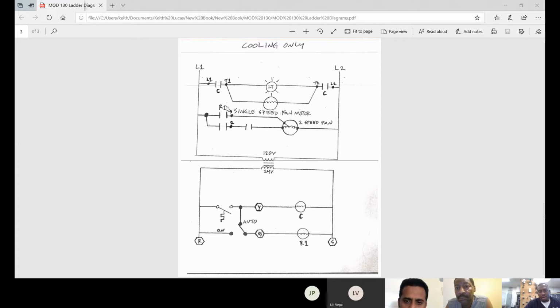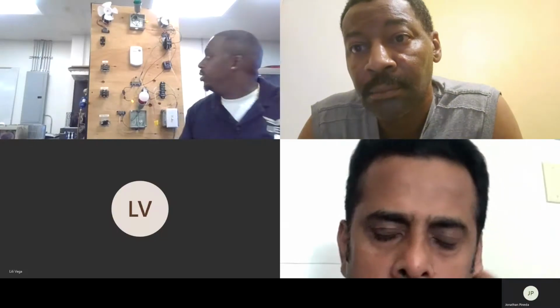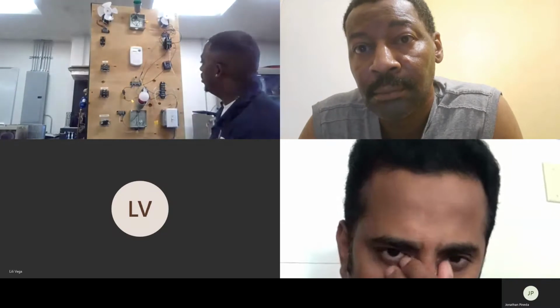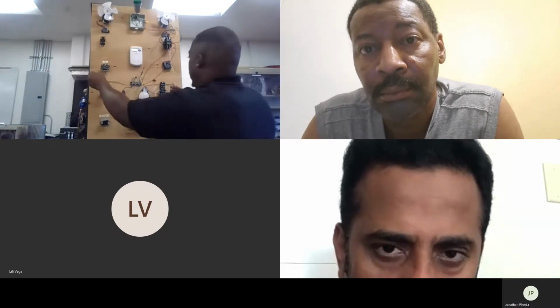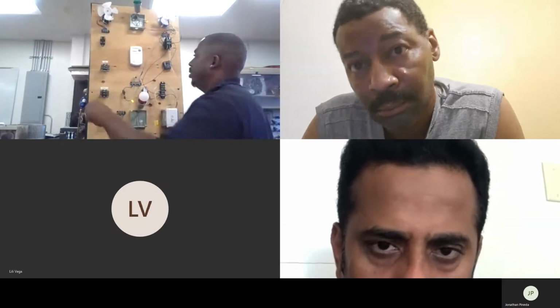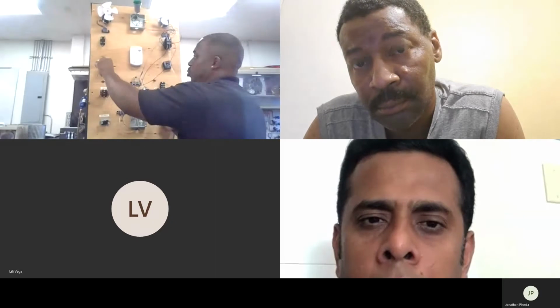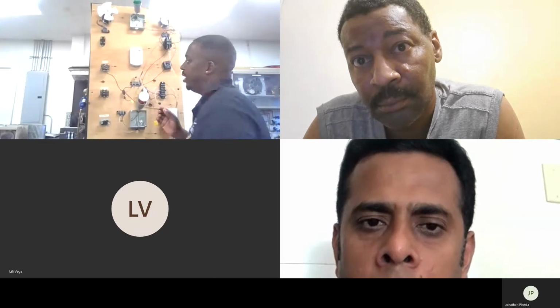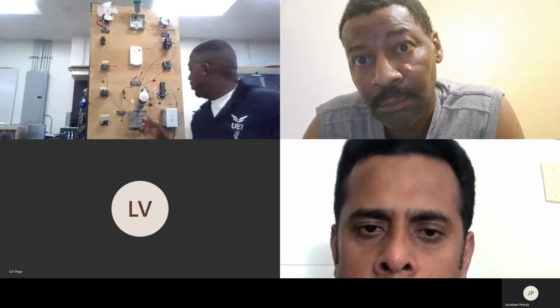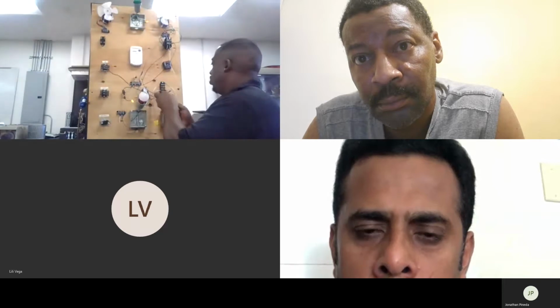Now we got to get our fan relay connected. We need an L1 to terminal 1 on relay 1, and that's going to energize our high-speed motor. So let's do that - I'm going to go to my terminal 1 on my relay, and this is going to connect to L1.